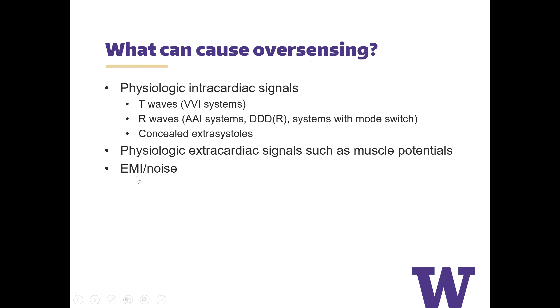So when do you use the magnet? You can use the magnet to assess for capture. You can use the magnet to break PMT, other causes of high rapidly paced ventricular rhythms. You can use a magnet to treat crosstalk inhibition, to treat oversensing so that it goes into an asynchronous mode essentially, and it's not sensing.